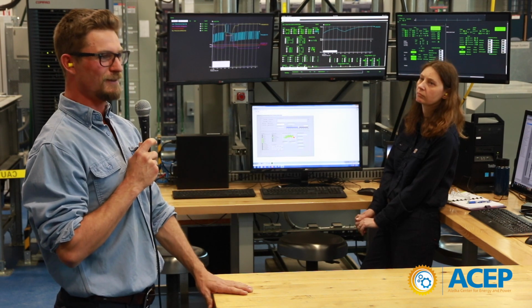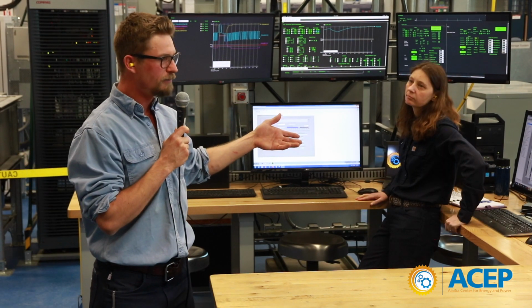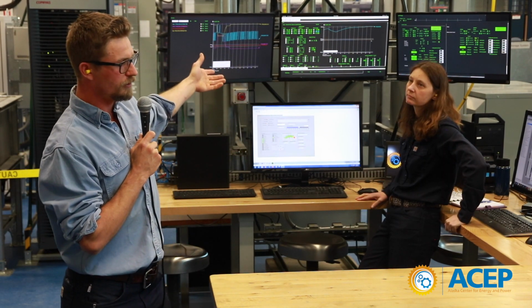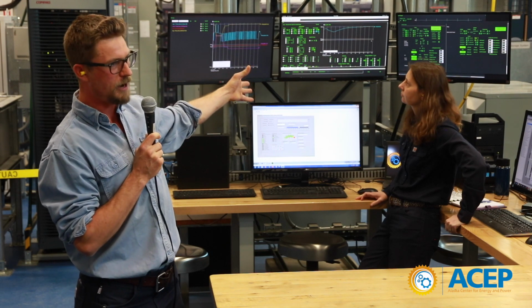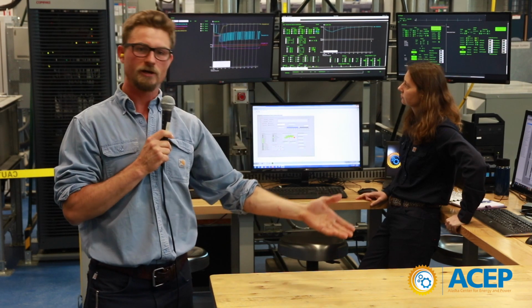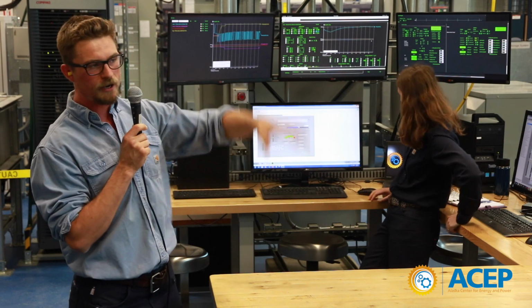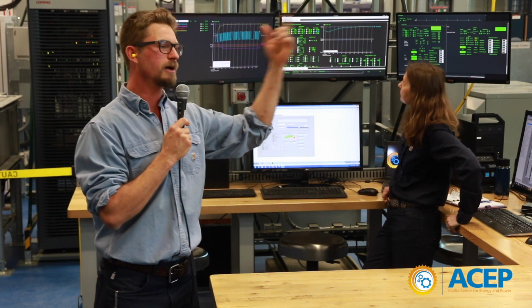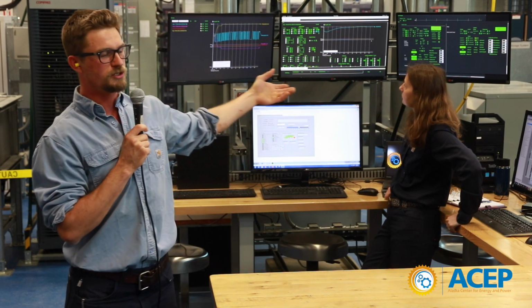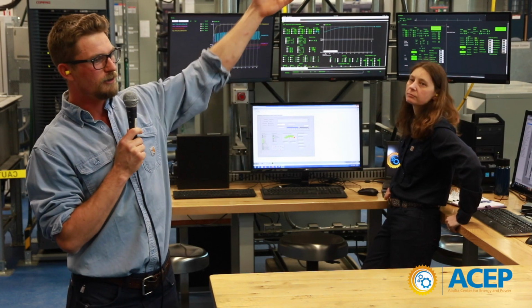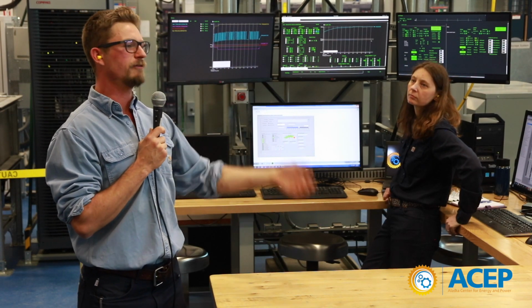That means you had a successful installation. If there's enough wind power, you can run with just your inverter and whatever energy you have stored in your battery. If your battery energy goes too low and your wind power drops, bring the generator back online, and the generator does what it's good at. When you have wind power again, bring it back off and run with your battery.